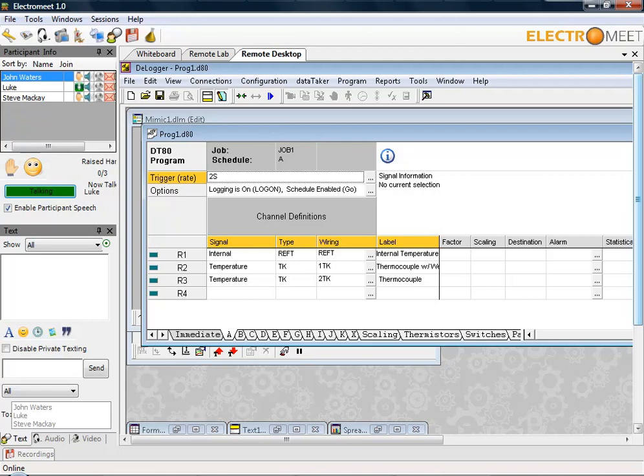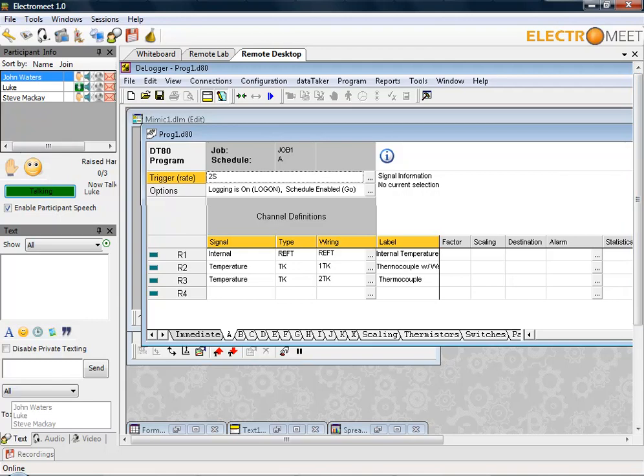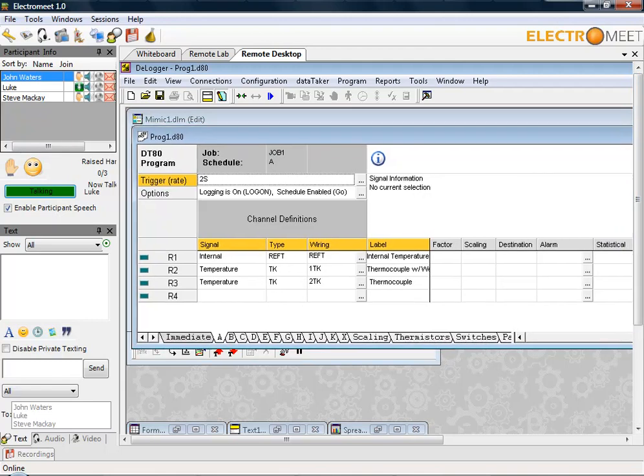The main prog1.d80 screen here shows us how we can program and configure the data logger. In this case, we've configured the trigger rate at two seconds, so the data logger will take samples every two seconds. We have three channels set up: one to take the internal reference temperature from the data logger to give us room temperature.